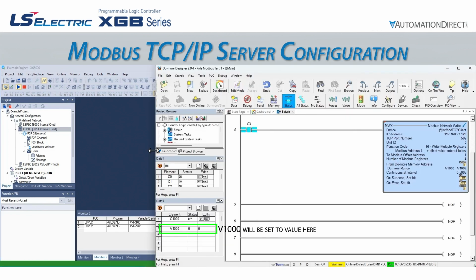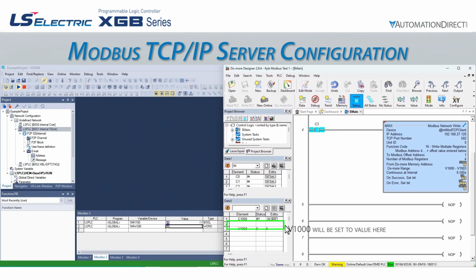If we write the first Modbus coil in the BRX to true, we see %MX100 go true. If we write 1000 into the first Modbus register in the BRX, we see %MW200 show 1000. Changing the Modbus function code would allow us to read data from the XGB in those ranges, or the %MX0 and %MW100 ranges.